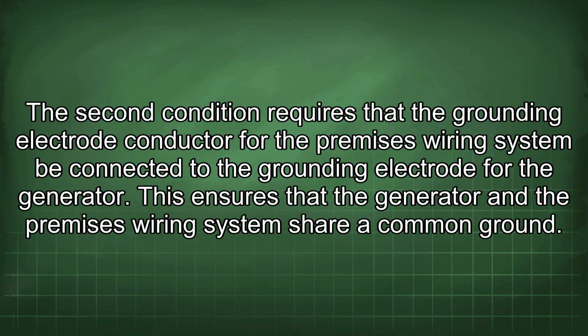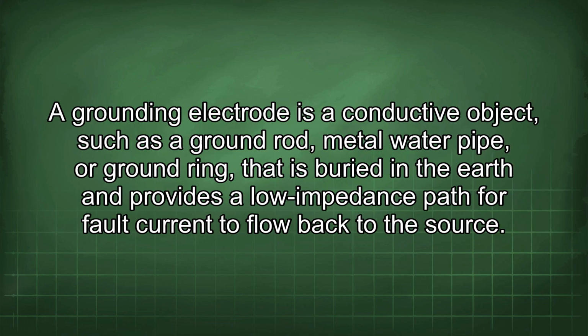The second condition requires that the grounding electrode conductor for the premises wiring system be connected to the grounding electrode for the generator. This ensures that the generator and the premises wiring system share a common ground. A grounding electrode is a conductive object, such as a ground rod, metal water pipe, or ground ring, that is buried in the earth and provides a low impedance path for fault current to flow back to the source.